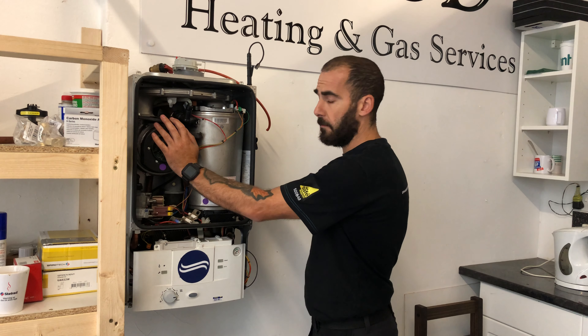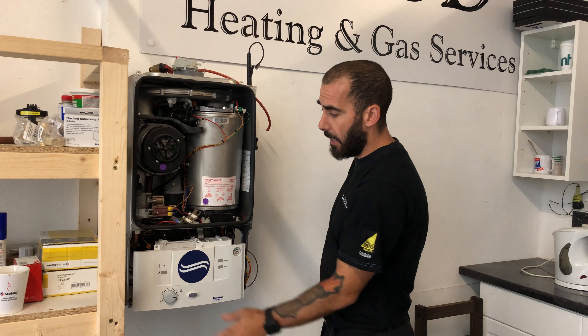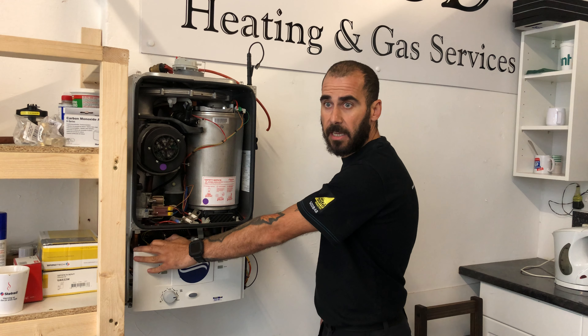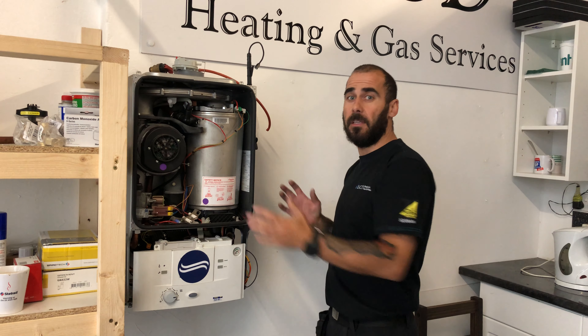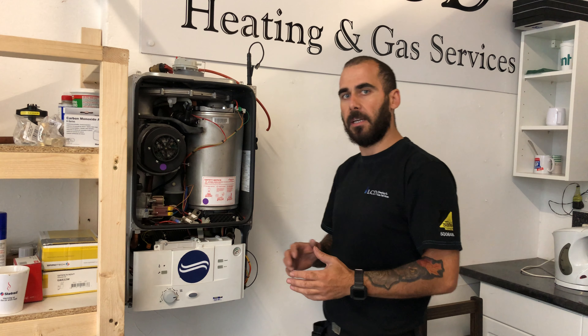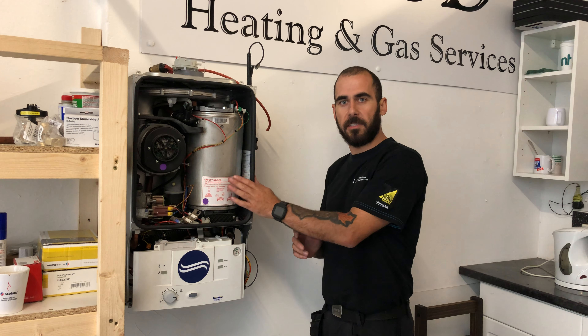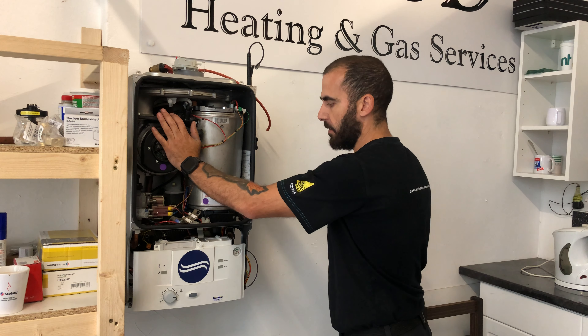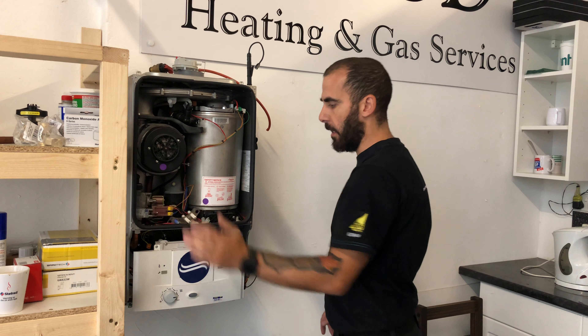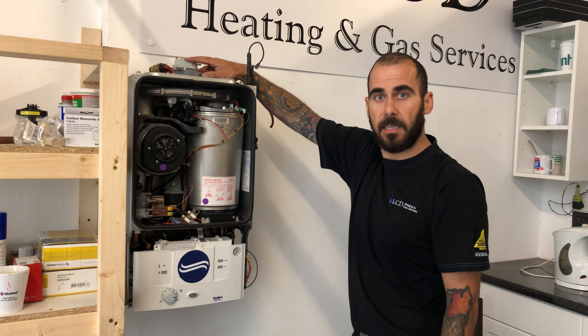You've got to check fan pressures, recheck the inlet pressure to make sure it's not under-gassed, and you clean out the siphon which is in here. Normally your boiler's got a cover on it, so if you're getting your boiler serviced and they don't even take the cover off, regardless of the manufacturer, that's not getting done right. Even with a one-year-old boiler, we have to take off the cover, check our readings here, clean out the siphon within the boiler, and obviously check that flue readings are acceptable.